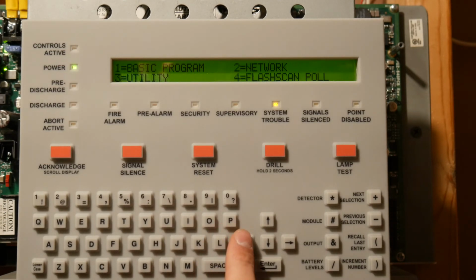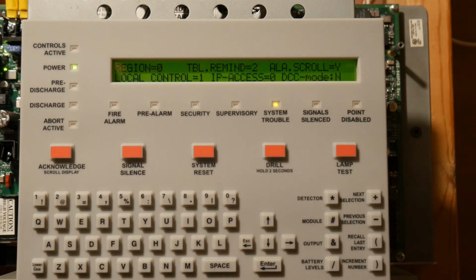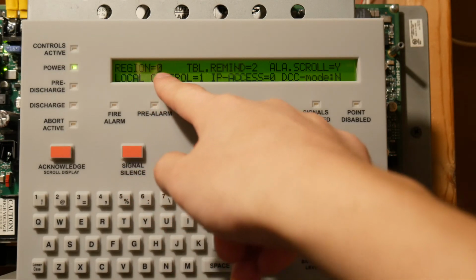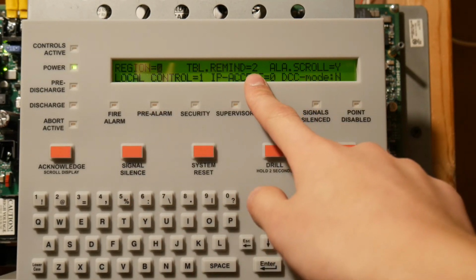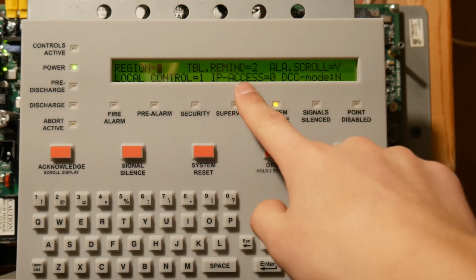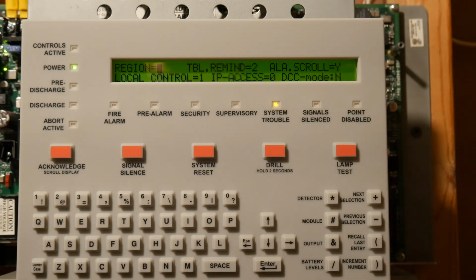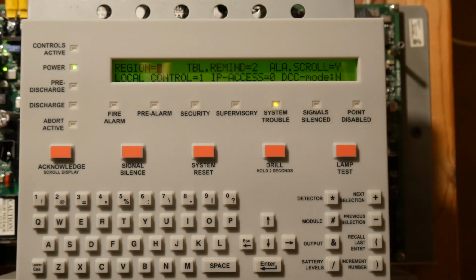Now let's go into, I think that's all. Oh no, it's not. So we're going to press 3 for utilities. Utilities is not that much you have to worry about. So basically region trouble reminder. If you set that at 0, that means there's no beeping. I like number 2 because it beeps every 30 seconds. I like that to remind me, even if there's a trouble, it'll still beep. ALA scroll basically means if there's another event that comes up, let's say there's a battery trouble and then a fire alarm comes up, the fire alarm event will display on the screen, so you don't have to press the acknowledge key to scroll through the event.